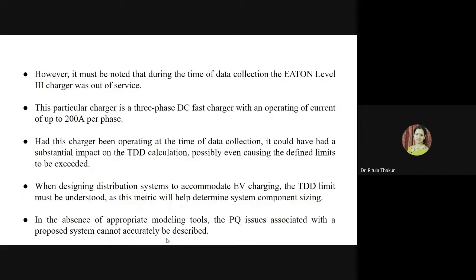Also, when they collected the data, the Eaton Level III charger was out of service for the calculation of TDD. So this may also be one of the factors why the TDD remained so low, because level 3 chargers, in which DC fast charging is there, produce the maximum harmonics because of the conversion from AC to DC. This particular charger is a three-phase DC charger with operation of current up to 200 amperes per phase.